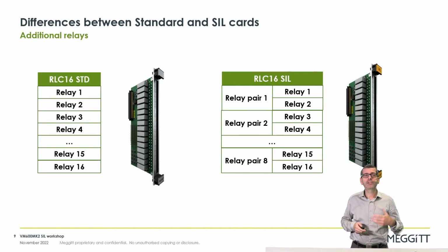That same principle applies to the RLC16. On the SIL version, we have 16 physical relays, but they have to be managed as 8 relay pairs. So we can connect a logical function from an MPC4 to one of those 8 relay pairs.